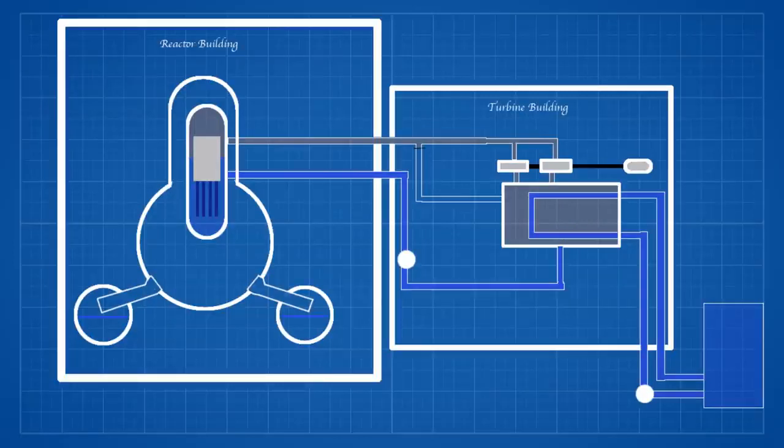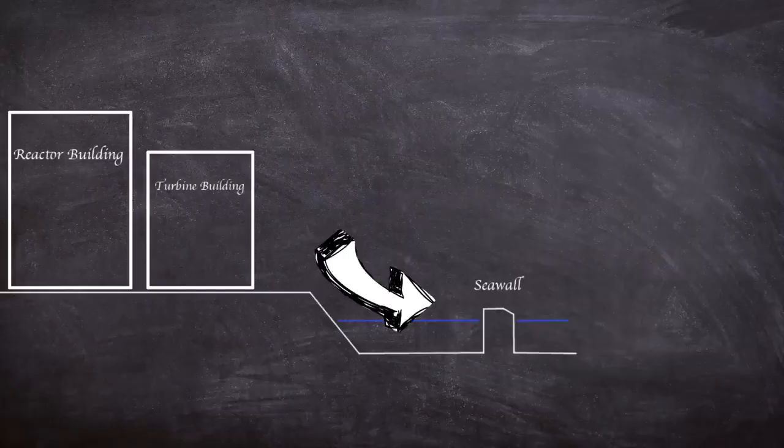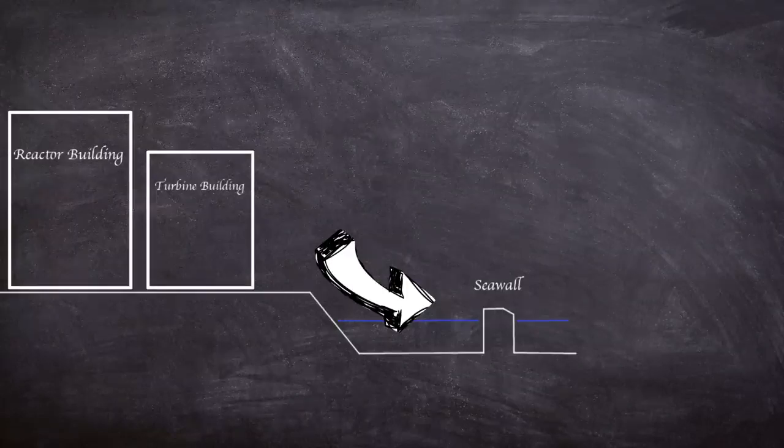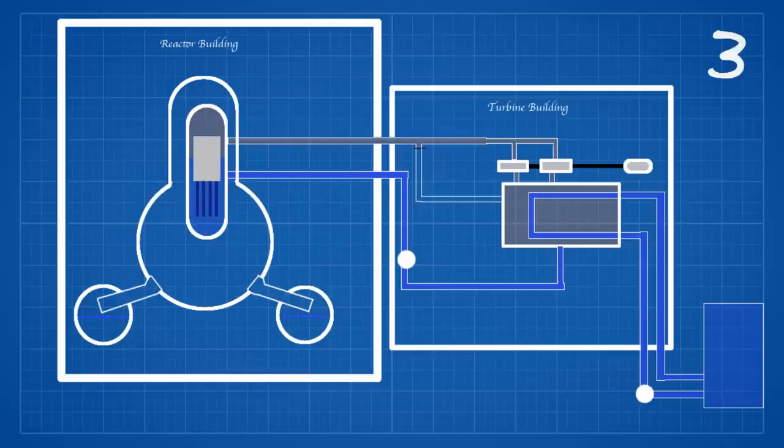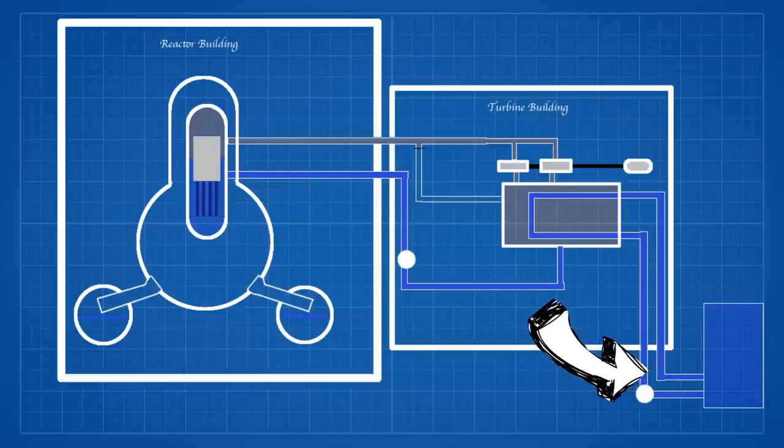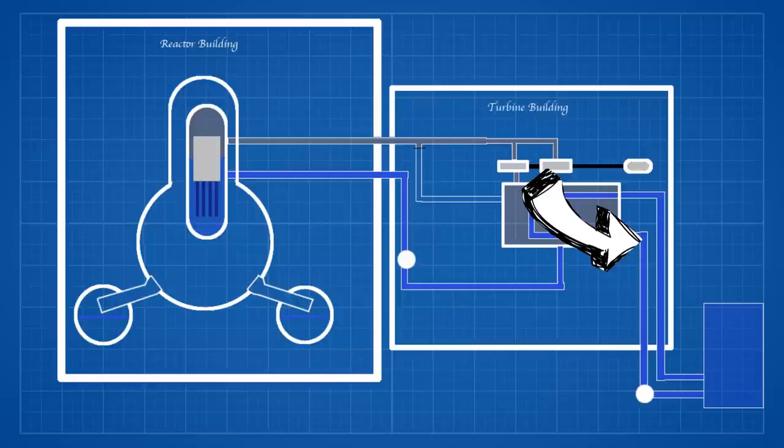At Fukushima seawater was used for condenser cooling water and auxiliary equipment cooling water. A seawall 10 meters high from the seabed was built in front of the power station with open channels behind it that led from the power plant to the ocean. Water was drawn in through sluice gates and pump rooms installed for each unit. From there it is transferred to the condenser by pumps installed in the pump rooms.